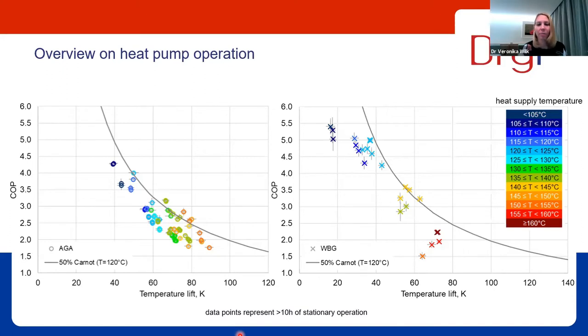I will just pick out some interesting areas in the diagrams, starting with the Wienerberger plant. So at a temperature lift around 40 degrees, we have a COP of 4.7. And here the blue ones are for a heat supply temperature of 120. And if we go to the highest temperatures, that one represents 160 degrees C, and there we have a COP of 2.2.